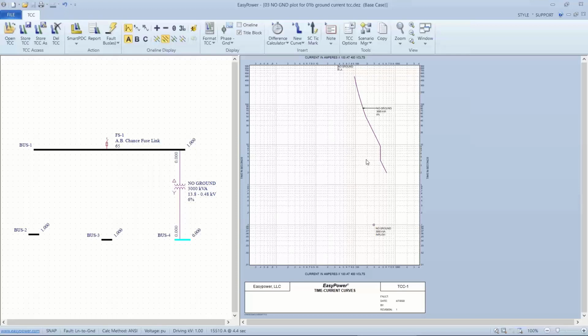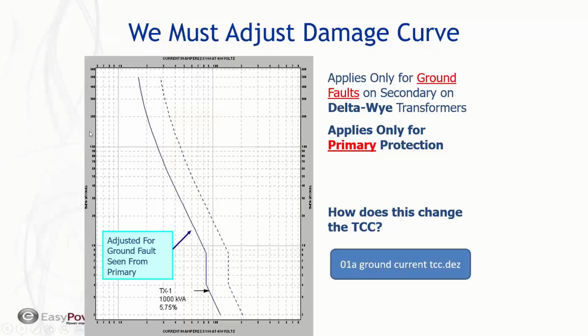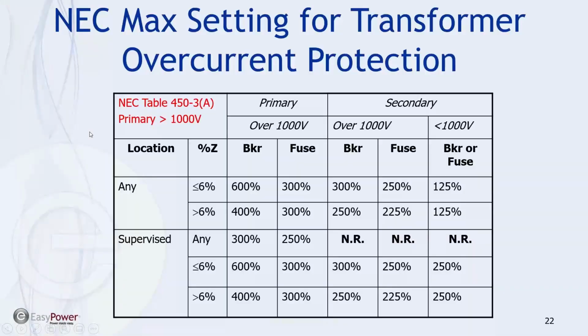So this whole derating ground fault, we're talking about the primary protection and a single line to ground where we have to derate the curve. Now, part of the National Electrical Code is overcurrent protection. Again, we'll get into this in more detail, but this is table 450-3, and talking about the primary protection and secondary protection. These numbers represent the maximum protection for a fault.